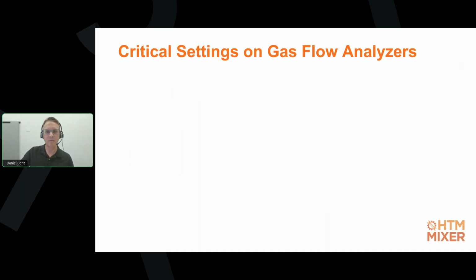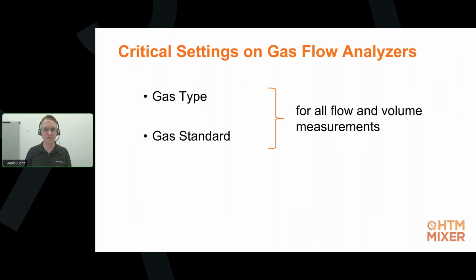So the most important settings on gas flow analyzers and ventilator testers are gas type and gas standard. Maybe those of you that have already tested ventilators have at least heard these terms. These two settings are crucial for all flow and volume measurements.